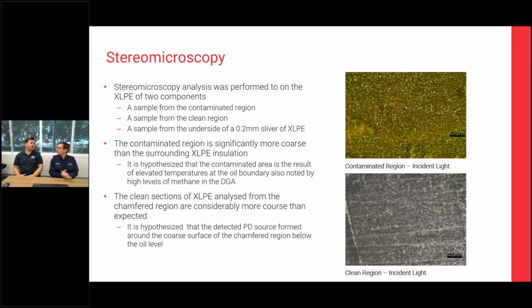So what we ended up hypothesizing is that rather than a single discharge site within the coarser regions going around the entire XLPE layer, it was more of multiple lower level discharges which were discharging out to the oil rather than within and degrading the insulation itself. Over time it was degrading a little bit, but it was more contaminating and breaking down the oil insulation rather than the XLPE itself. And that would explain, similar to our phase resolved patterns, why it was very lopsided, because it's on the outside of that insulation layer, as far from the live component as it could get.